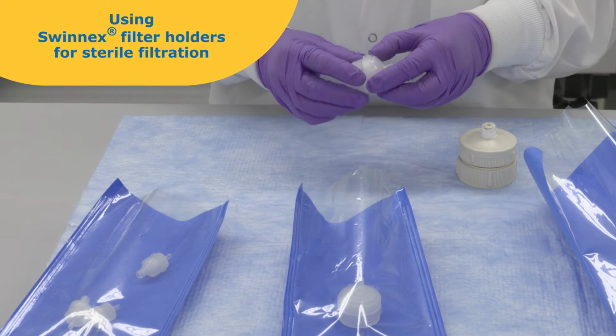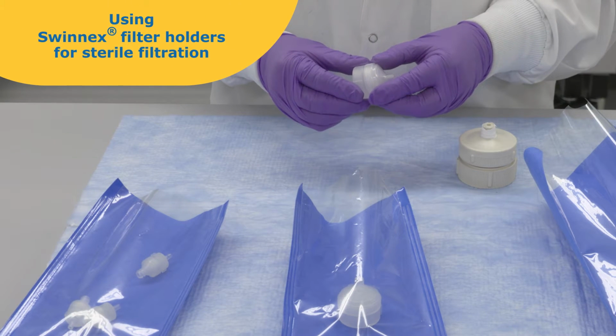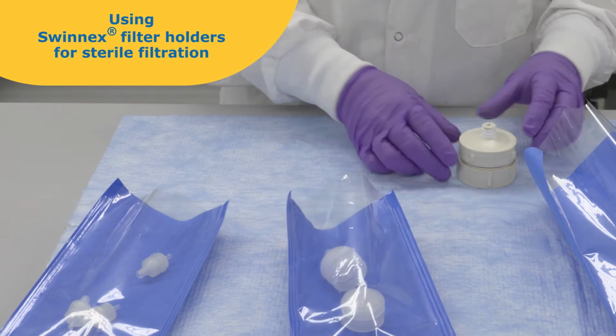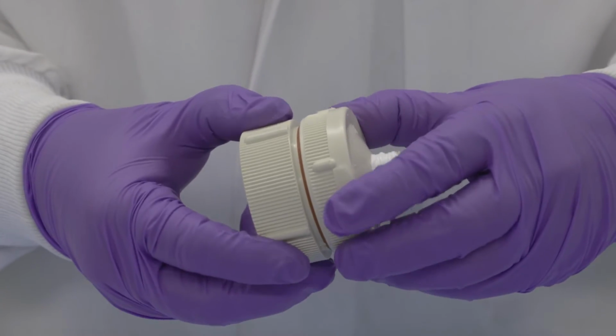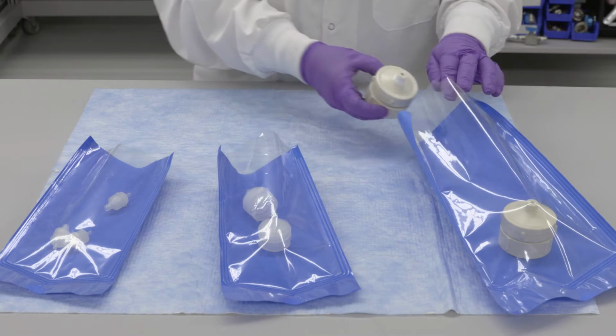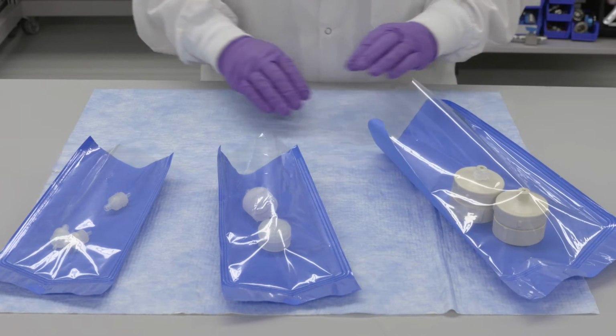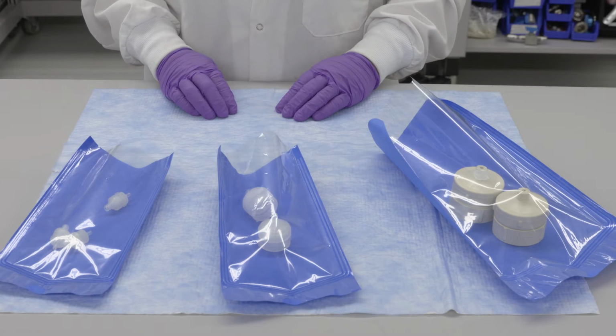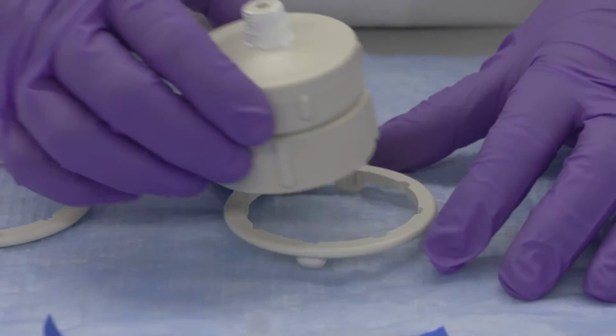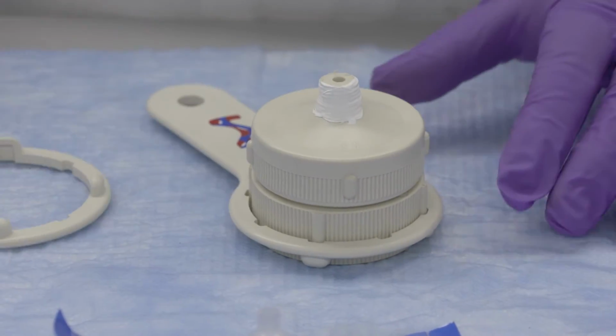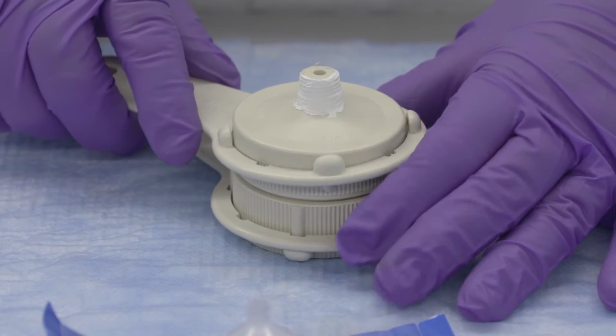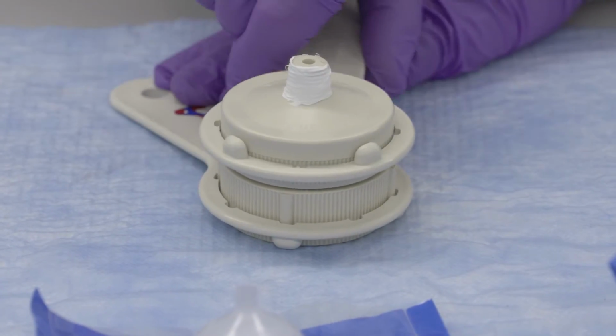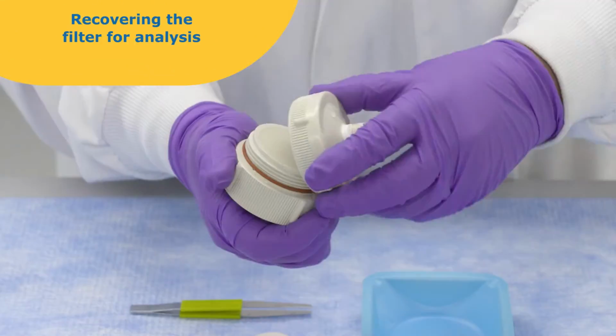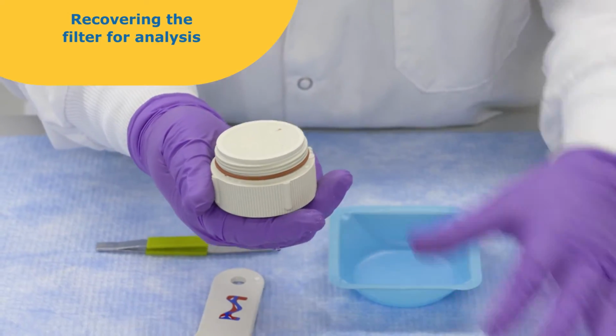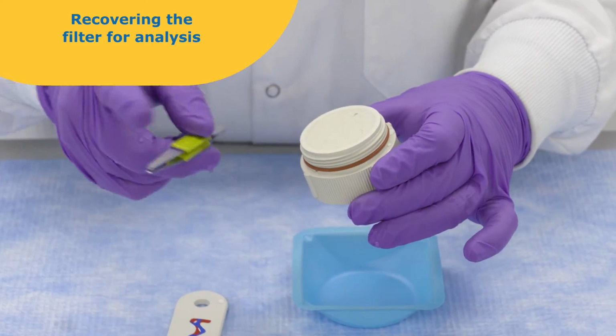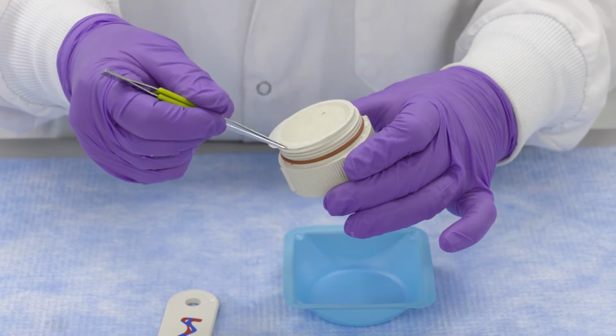For sterile applications, holders can be assembled with a filter in place and then autoclaved. Hand tighten until it just meets resistance, so the inserted filter does not shift, and use a liquid exhaust or slow typical cycle. After the autoclave cycle, cool to room temperature before fully tightening the unit. Use aseptic technique when handling. The filter may be recoverable for further analysis or other applications as your procedure dictates.